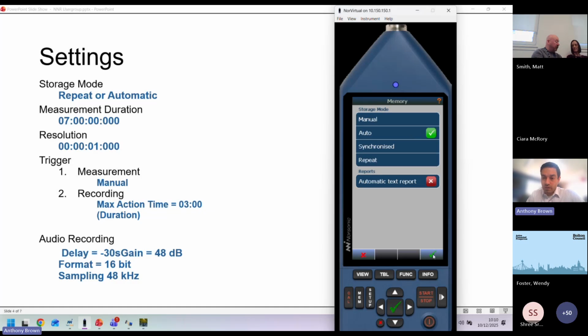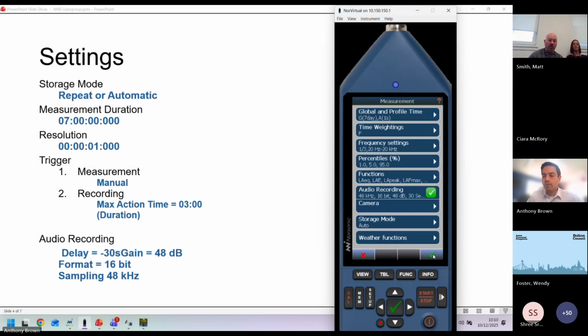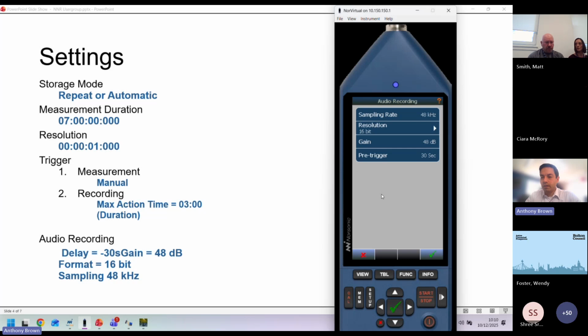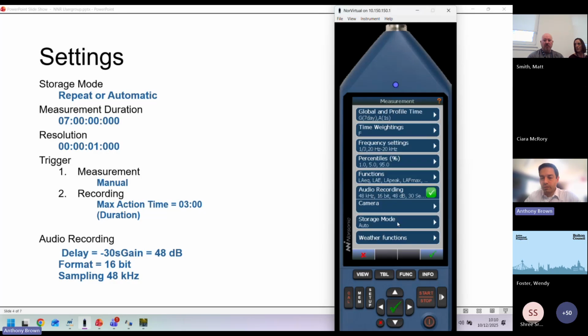I will go with auto because I just need a 7-day measurement, but you might go for repeat. So those are the settings in the measurement: global and profile time set to 7 days, 1 second. The next important one was the audio recording, making sure it's set to 48 kilohertz, 16-bit, 48 dB gain, and the pre-trigger. Then your storage mode should say auto or repeat at the bottom here.